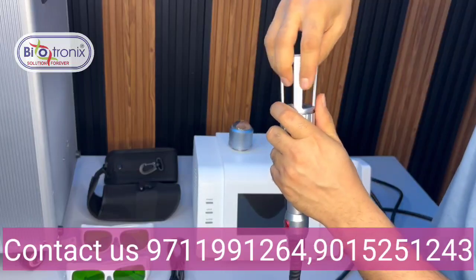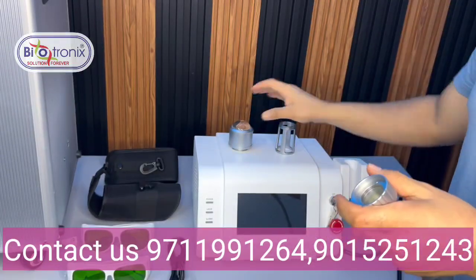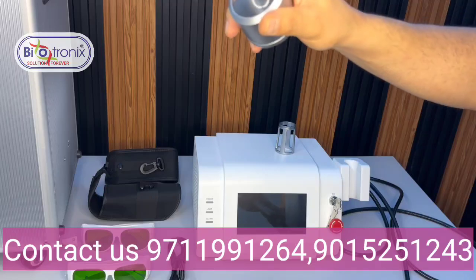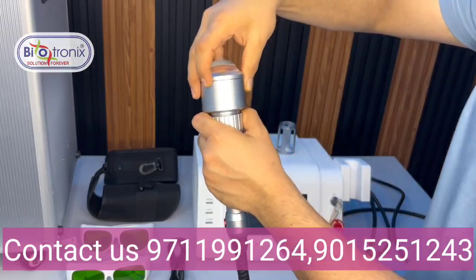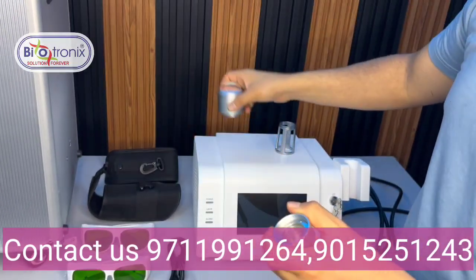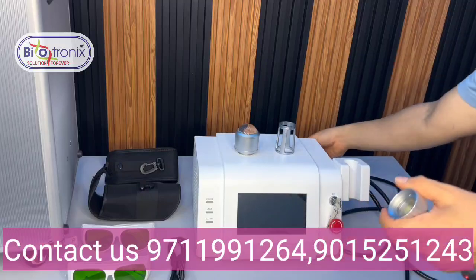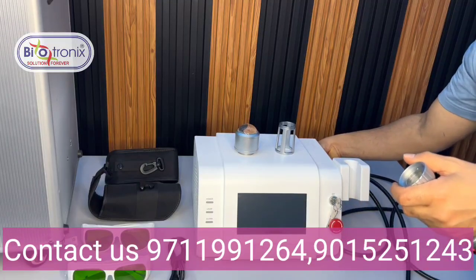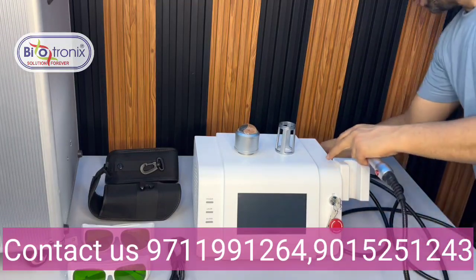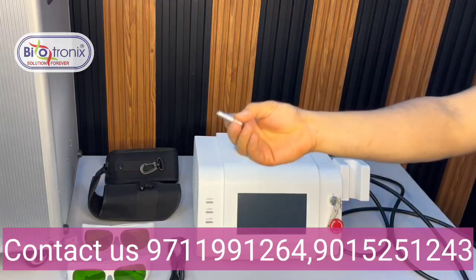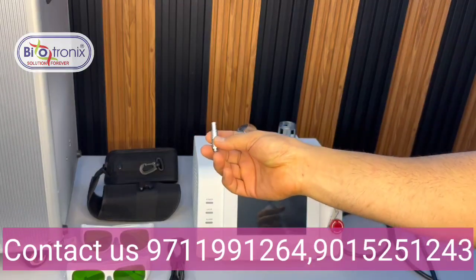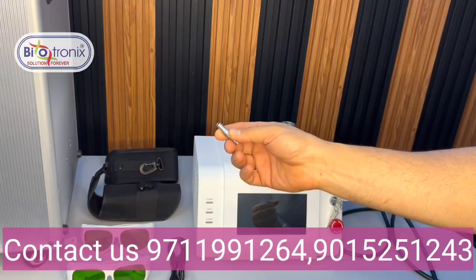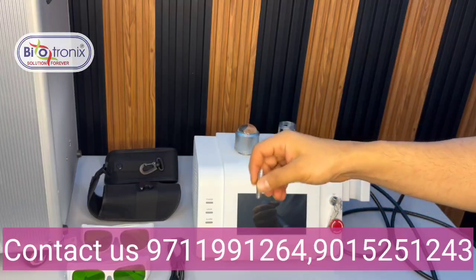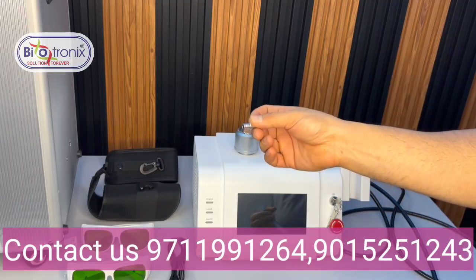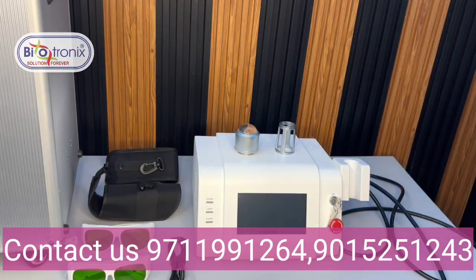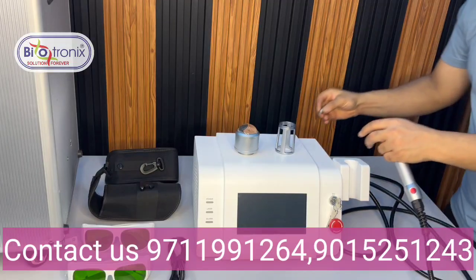Now I am plugging it out, and this is the second attachment with the lens, and you can see it can be plugged in like this and can be used. There is an interlock switch. This is the interlock switch that has to be connected at the base on all the laser devices. If it is not there, the device will not turn on and it will not provide the beam. So that interlock switch has to be plugged in from behind.